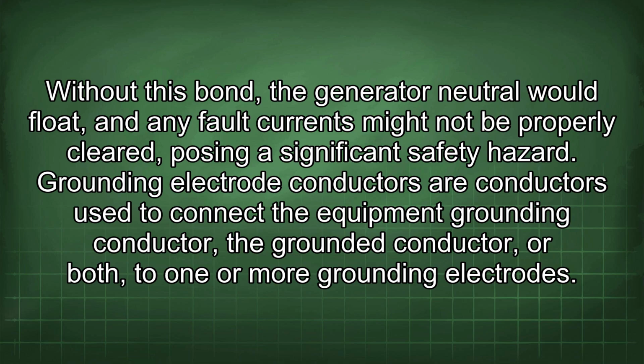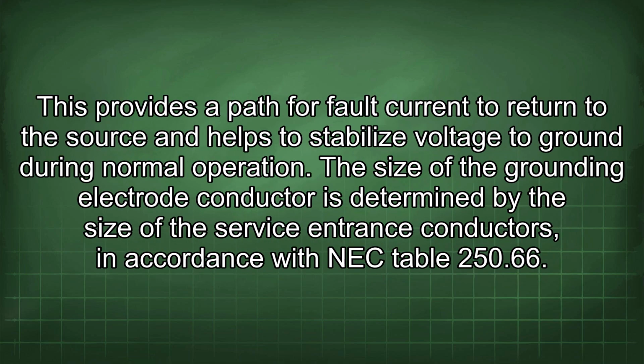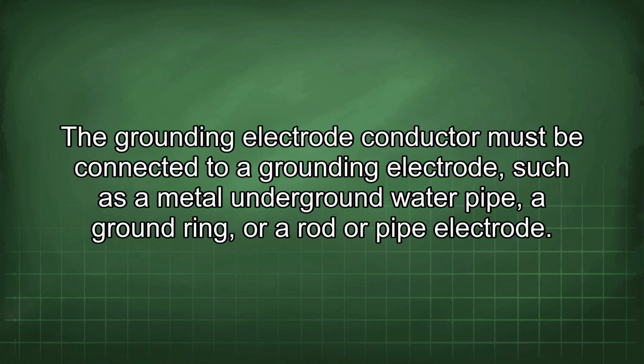Grounding electrode conductors are conductors used to connect the equipment grounding conductor, the grounded conductor, or both, to one or more grounding electrodes. This provides a path for fault current to return to the source and helps to stabilize voltage to ground during normal operation. The size of the grounding electrode conductor is determined by the size of the service entrance conductors in accordance with NEC Table 250.66. The grounding electrode conductor must be connected to a grounding electrode, such as a metal underground water pipe, a ground ring, or a rod or pipe electrode.